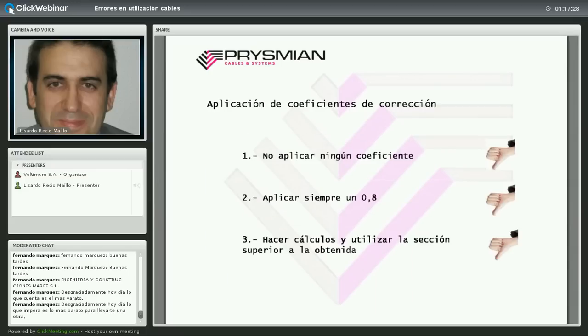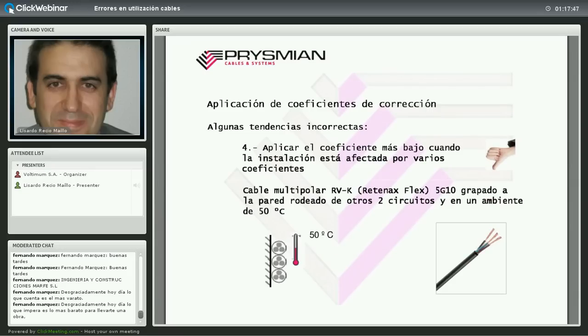Aplicación de los coeficientes de corrección: tendencias incorrectas. Una de ellas es no aplicar ningún coeficiente, o aplicar siempre un 0,8, o al calcular una sección aplicar siempre la inmediata superior cuando a veces puede valer la calculada o hacer falta dos saltos. Otra tendencia incorrecta es aplicar solo el coeficiente más bajo cuando la instalación está afectada por varios: si uno es 0,7 por temperatura y otro es 0,8 por agrupamiento, hay que aplicar los dos: 0,7 × 0,8 = 0,56.